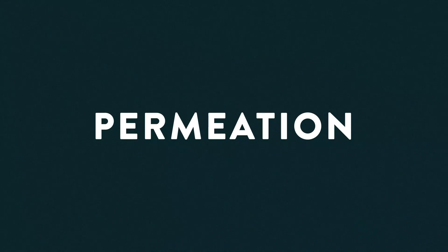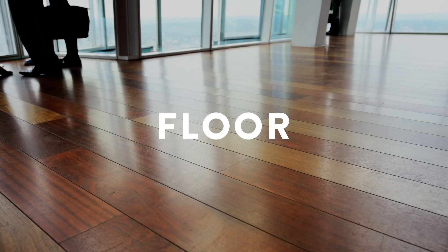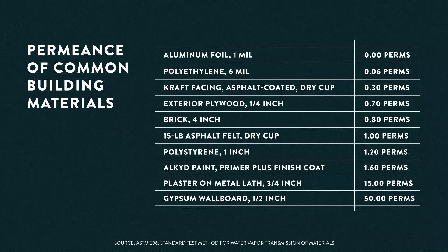Our next one is permeation — the flow of moisture in and out of building materials. If the humidity is high in a space, it's naturally going to get absorbed into the floor, into the carpeting, into the walls, into the building materials and the furniture, and eventually it's going to get released when the relative humidity goes down. Once in a while, we even get moisture traveling from outside through the building material and into the inside. Not a large load, but still something we want to talk about. If you've got a large concrete floor or thin walls, you should let me know so we can figure out if that's going to be an important load to calculate.